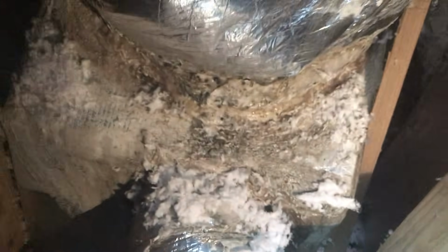This is R6 insulation. Currently in the attic, we are at a 77.7 degree dew point. So any surface that gets below 77.7 degrees will start to sweat. So you know that air in the ductwork is going to be 48 degrees or so, and the R value on all this ductwork just isn't meeting it. So we kind of have two options: decrease dew point or increase insulation.